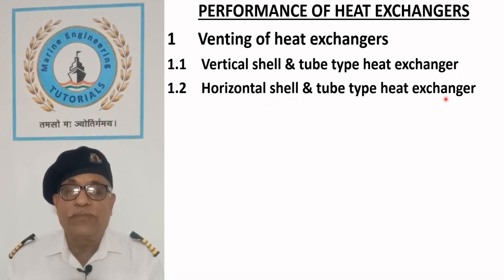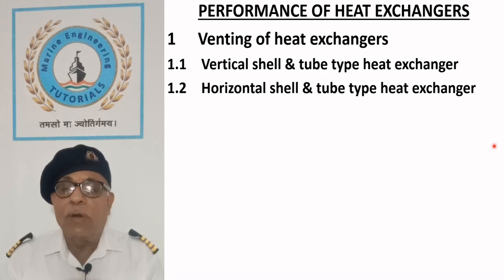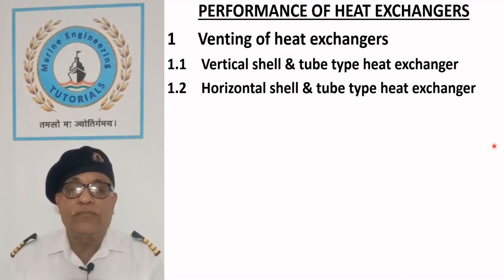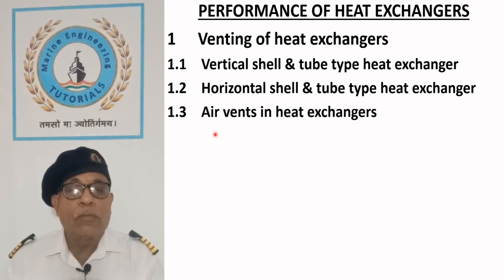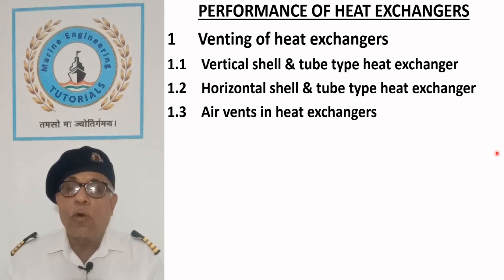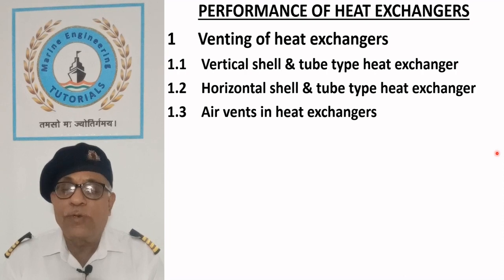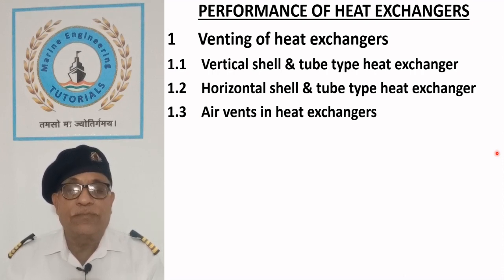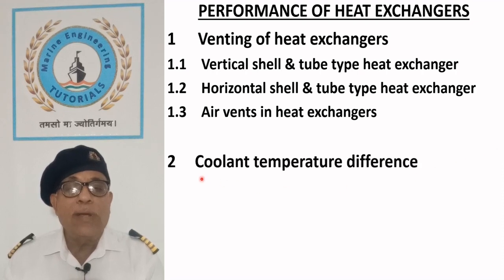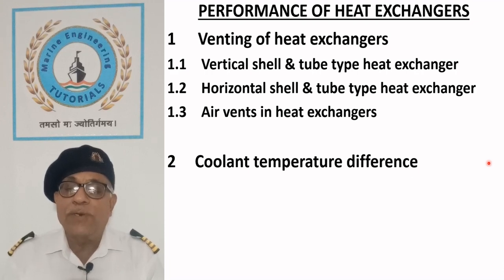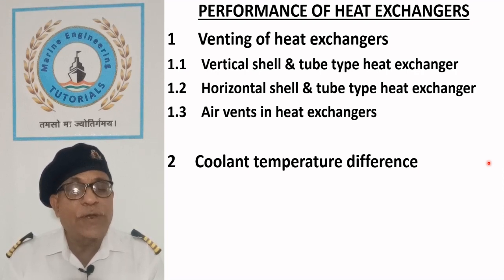Horizontal shell and tube type heat exchangers. Cooling water inlet from the bottom and outlet from the top, particularly in multi-pass arrangement, achieves automatic venting with horizontally mounted shell and tube type heat exchangers. Air vents in heat exchangers. Small amount of air trapped in the upper part of the shell and water boxes should be removed from the air vents, specially equipped for this purpose. Coolant temperature difference. Usual temperature difference between inlet and outlet of the coolant should be about 5 to 6 degrees centigrade, which is able to indicate whether the performance of heat exchanger is satisfactory or not.